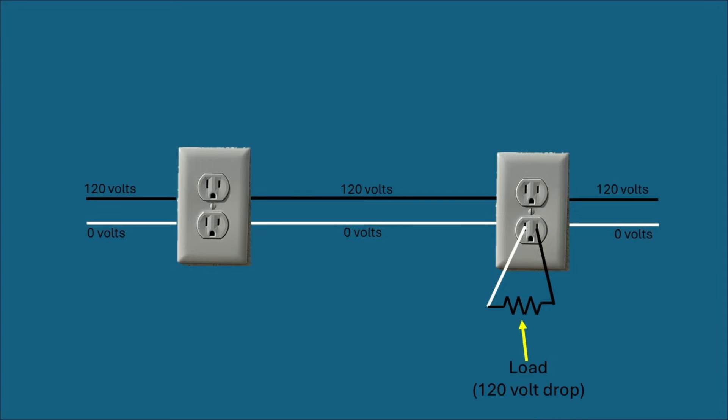Before I show you on my test board, let me show you using a diagram what happens when we have an open neutral and a bootleg ground. So here's a just a typical circuit. We've got two receptacles and we've got a load plugged in. So you've got 120 volts on all those black hot wires and you've got zero volts on the neutral wires. You can see the load plugged in and across the load you have a 120 volt drop. So that's why on the neutral side even with the load you've got zero volts.